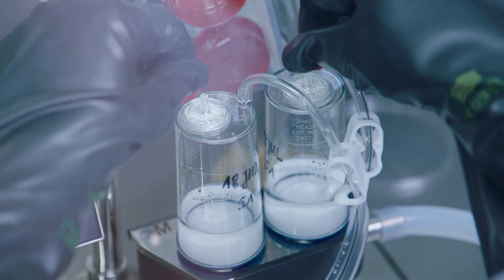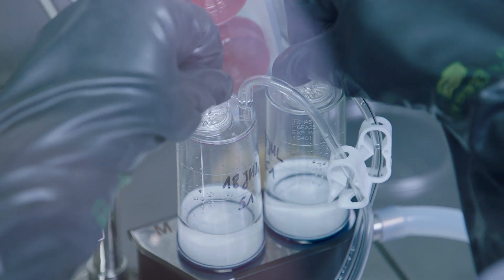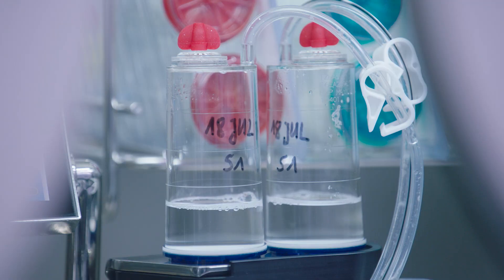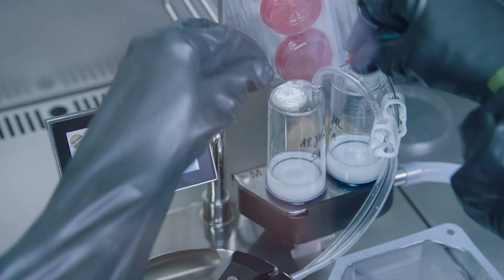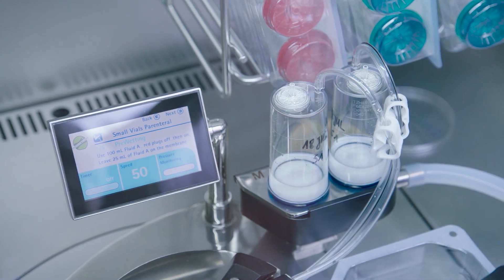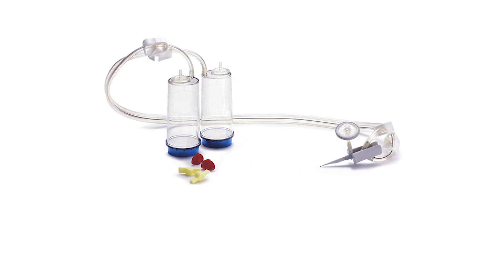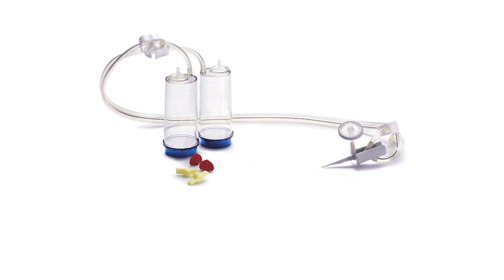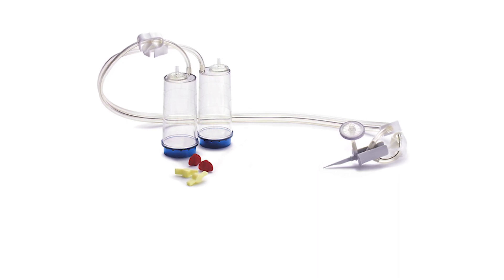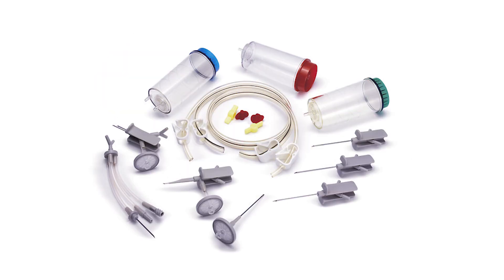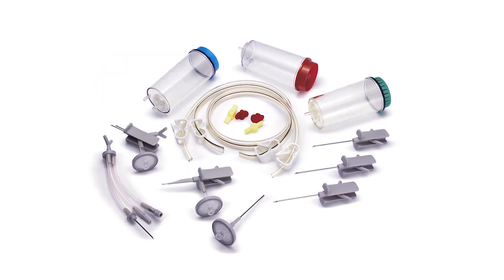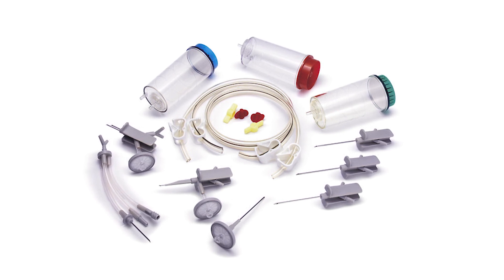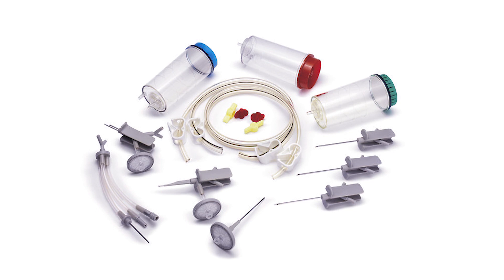The canister vents are closed with red plugs to create pressure, which starts the fluid filtration. After half of the fluid has been filtered, in order to keep the membrane wet, the red plugs should be removed. Millipore Sigma offers a large portfolio of Steritest devices optimized for secure sterility testing. Our solutions simplify your process regardless of container shape, challenging sample compositions like antibiotics and oily products, or if dissolution is required.